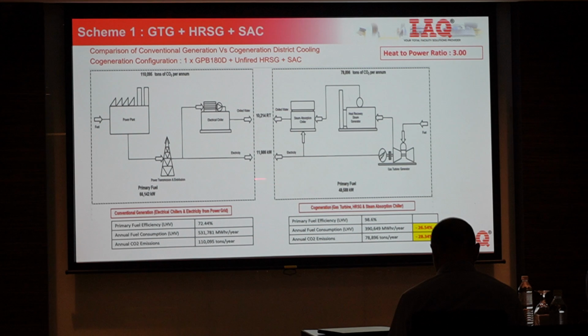This is a comparison for a smaller machine, the GPB180D, around 16 megawatts of power. This compares the whole generation system versus the conventional system. For the conventional system, you are importing power from TNB; for chill water generation, you use an electrical chiller, or if you need steam, a boiler. For us, it's basically injecting fuel into the gas turbine HRSG and using a steam absorption chiller. You can see the primary fuel efficiency is 72.44% for the conventional system, versus 98.6% for ours — an efficiency improvement of 26%.